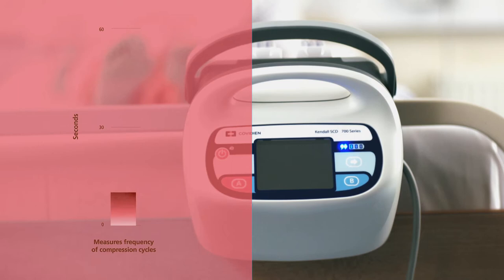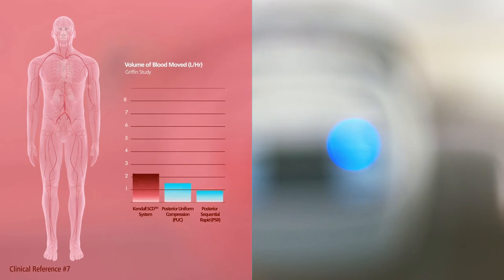VRD works by measuring the time it takes for a patient's veins to refill with blood after being compressed, and then setting the frequency of compression cycles based on the patient's particular venous refill time, anywhere between 20 and 60 seconds. This number is automatically recalculated every 30 minutes.